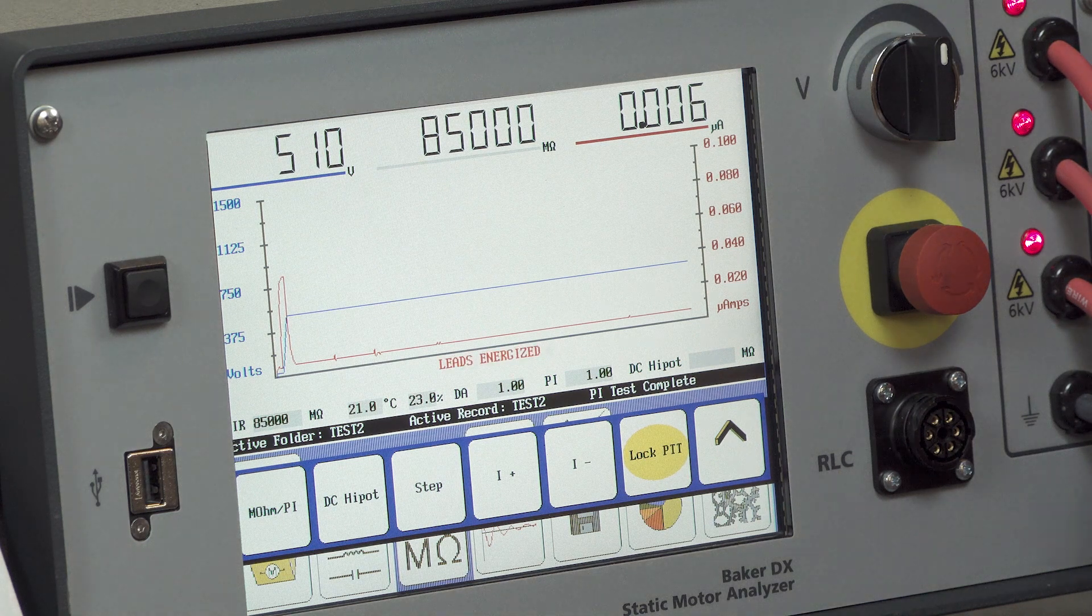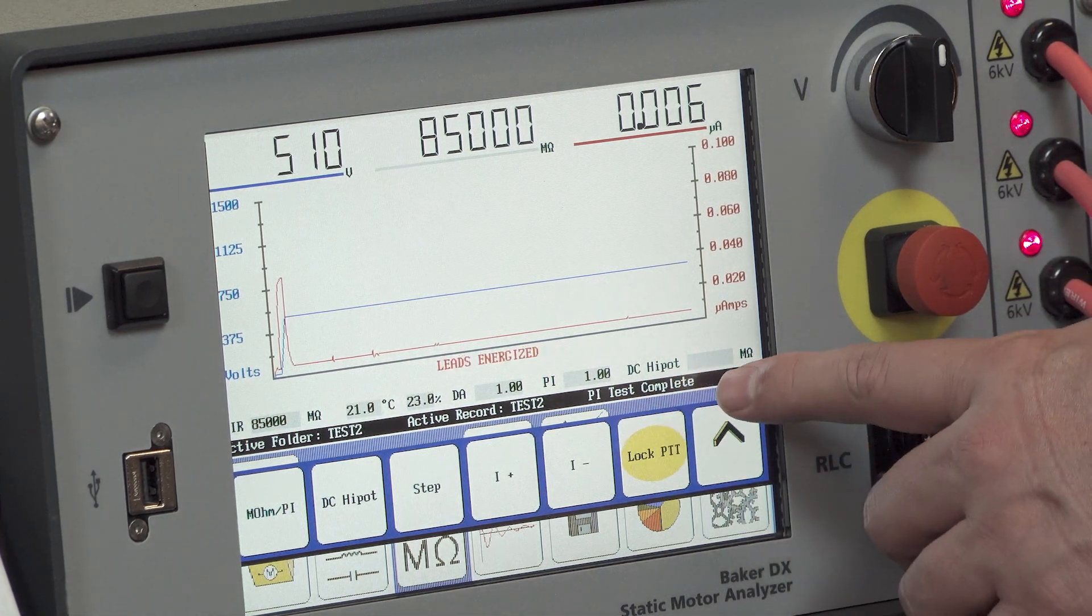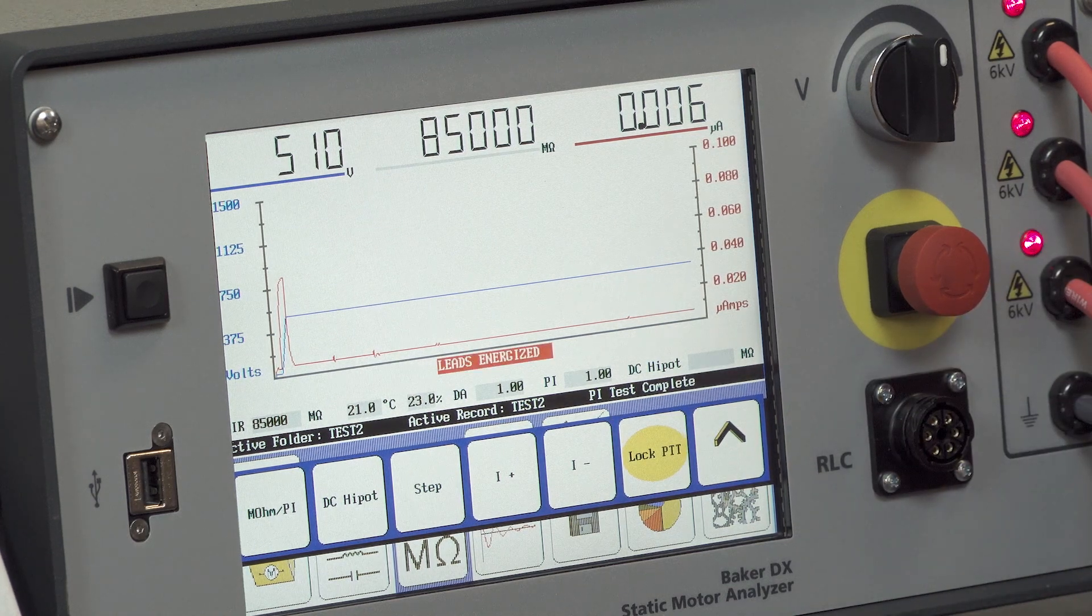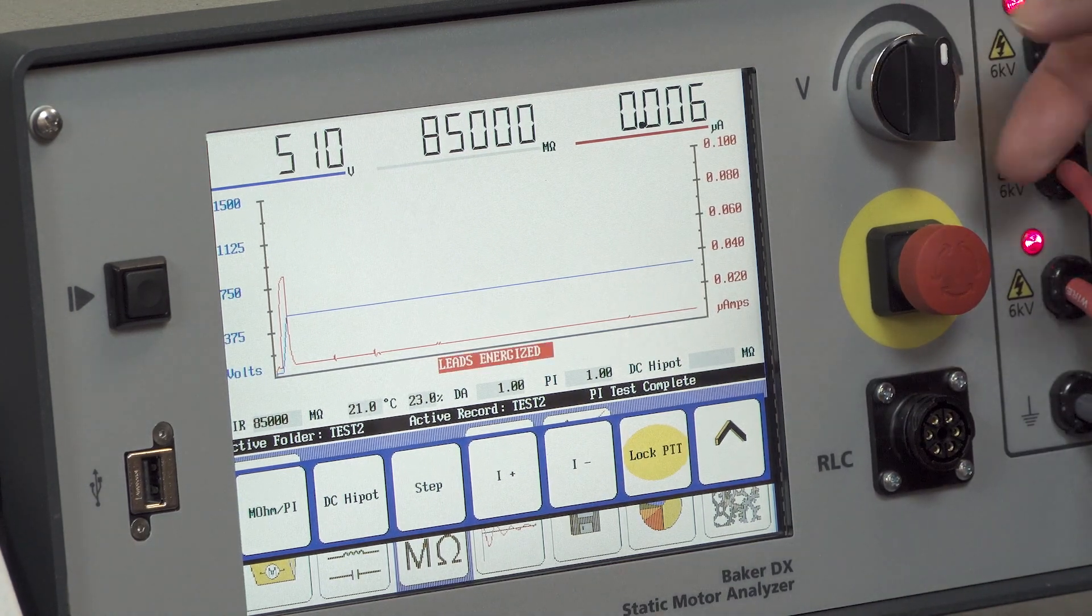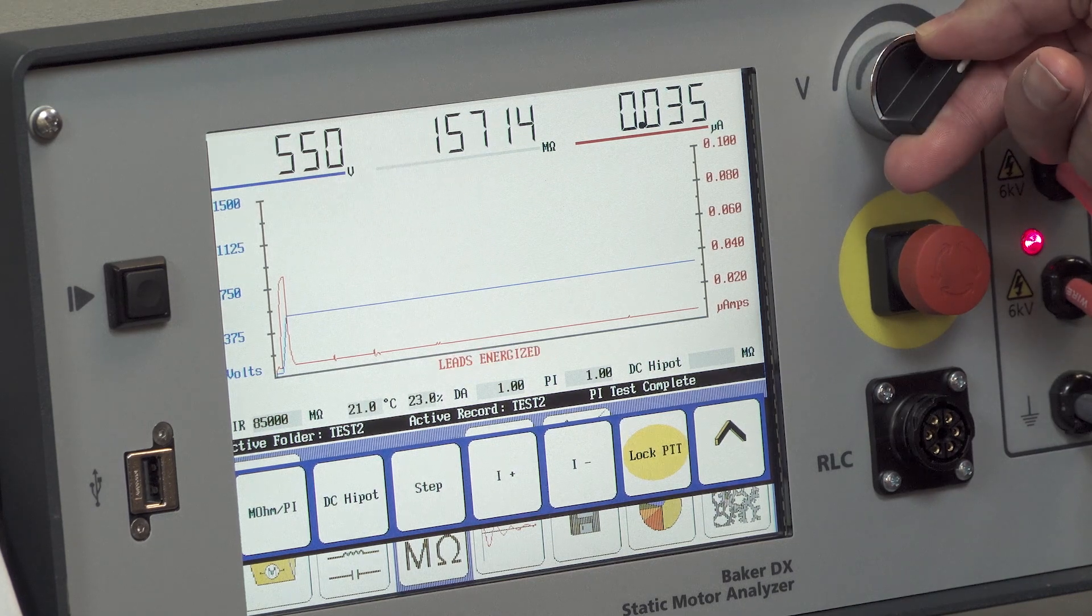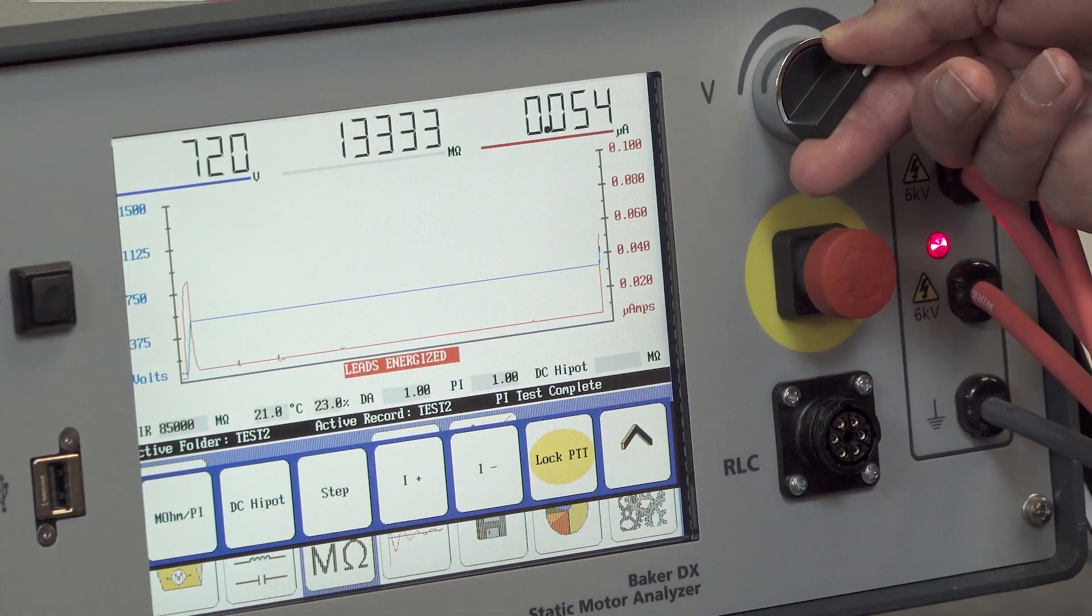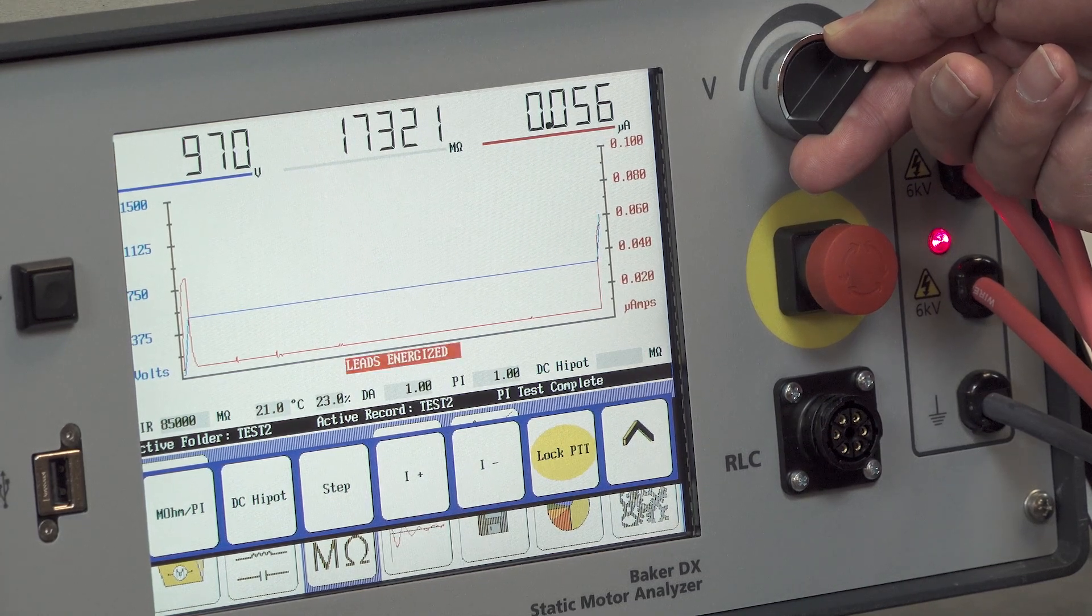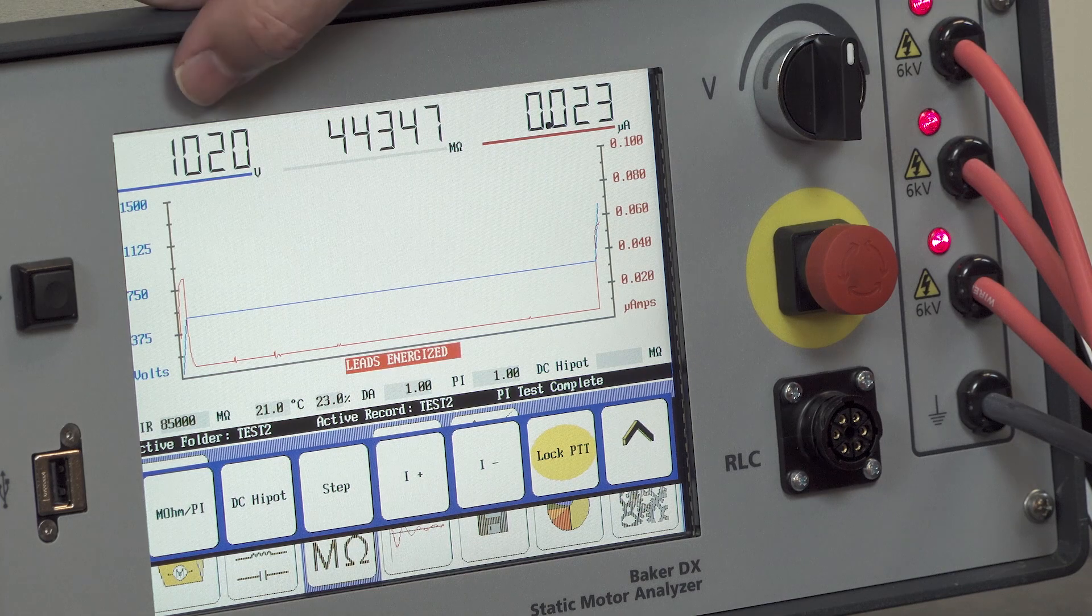Okay, now that the PI test is complete, we'll see PI test complete message in the lower right hand corner. We're ready to proceed on with a high potential test. Do that by simply increasing the voltage to the desired level. In this case I'm going to a thousand volts, I'm going to pause.